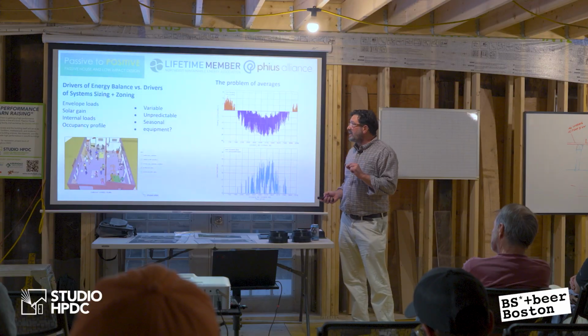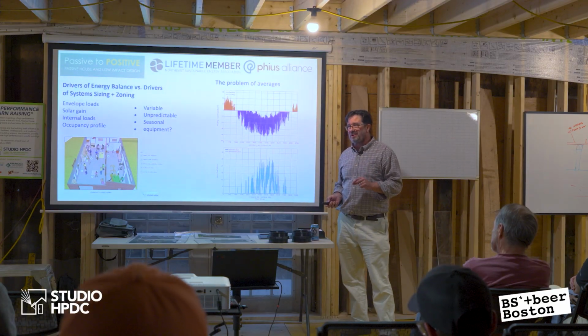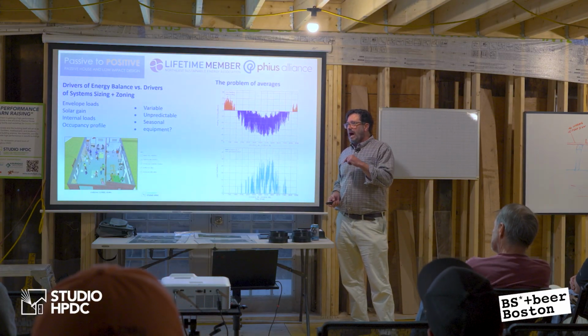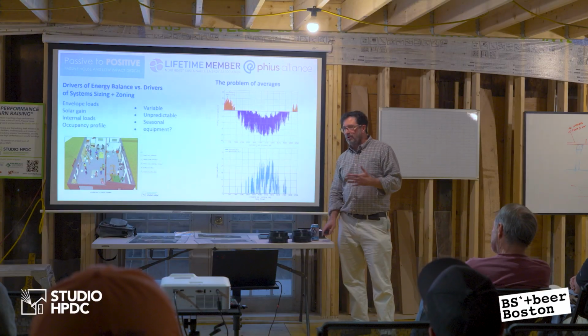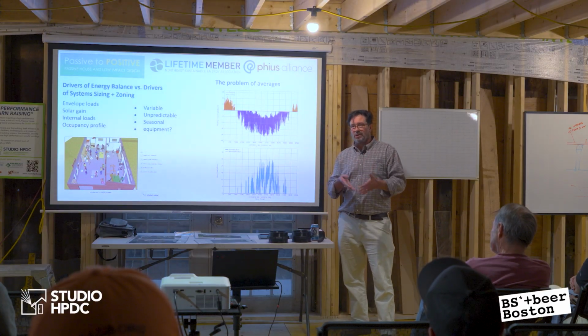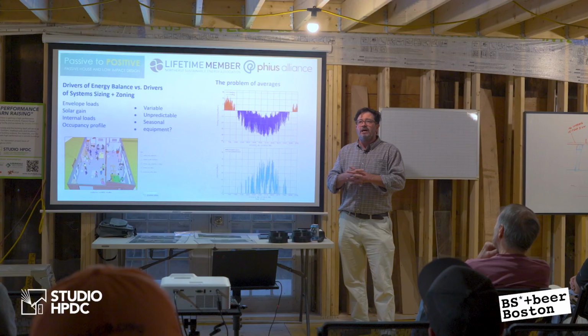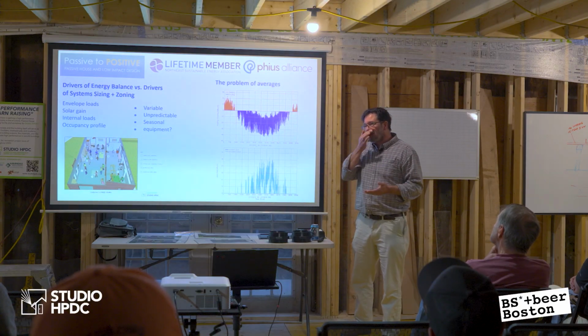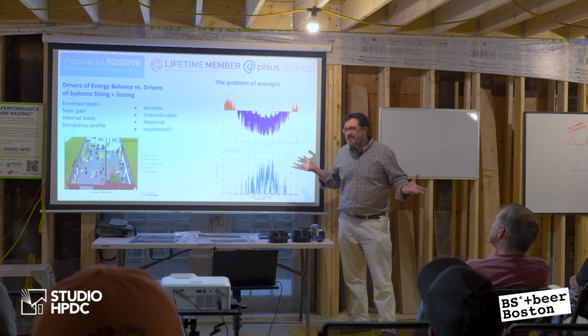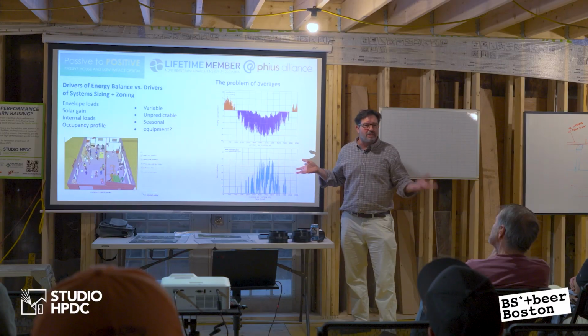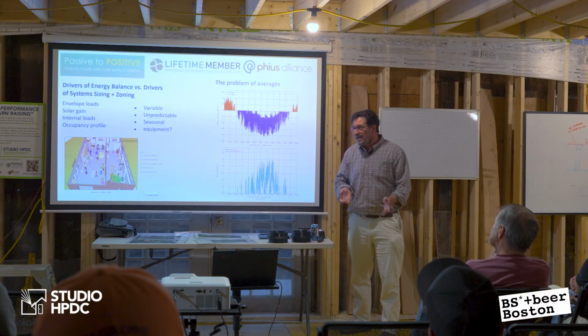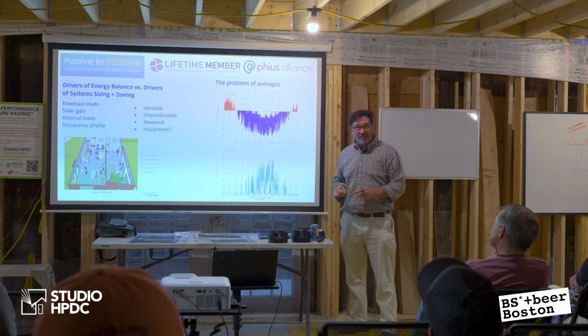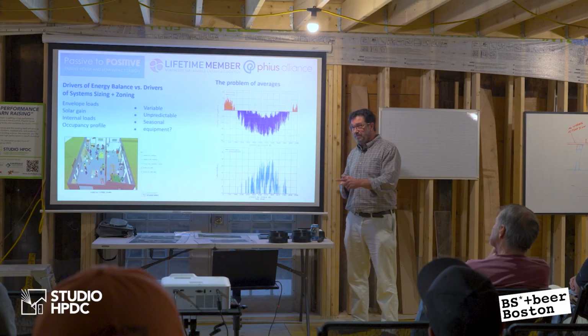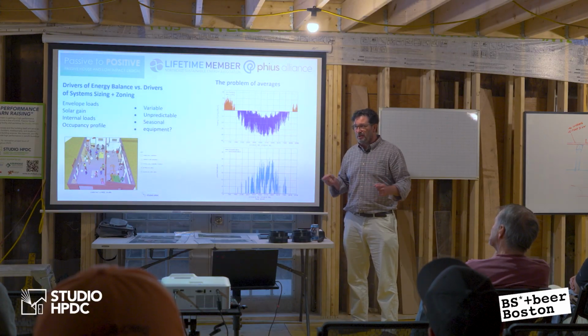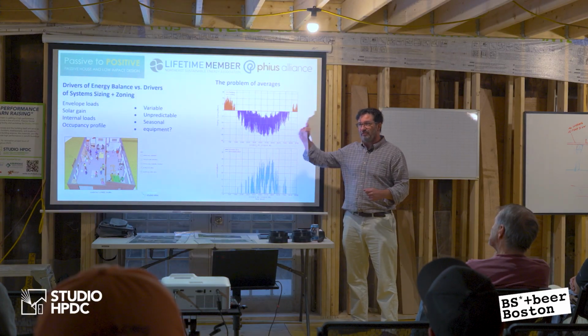When I say the map is not the territory and our perception is our reality divided by our perceptual limitations, you might just say, oh, that's a nice philosophical conceit, Michael. You always have to have something philosophical to say about these issues. And I can say, okay, maybe it's not that important, except that if you learn, as I did the other day, that high performance heat pumps have a different coil design to deliver better sensible returns so they can have a higher efficiency rating, they drop out less moisture.